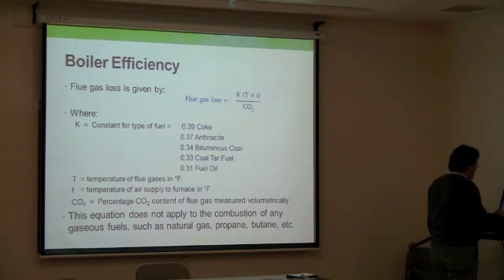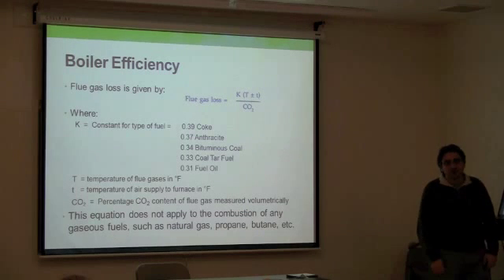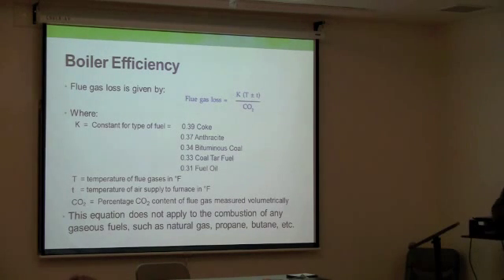Those kinds of things are in your control, basically. And when you do energy auditing, you have to do that. One of the things you have to do when you're dealing with the boiler is you always have to measure the content coming out of the flue gas. See how much CO2 you have, how much NOx you have, how much CO you have, because that tells you how clean or how good your combustion is. Because if your combustion is not good, you're wasting your money. That's the first level that you have to go to. It's not that expensive to do, actually.